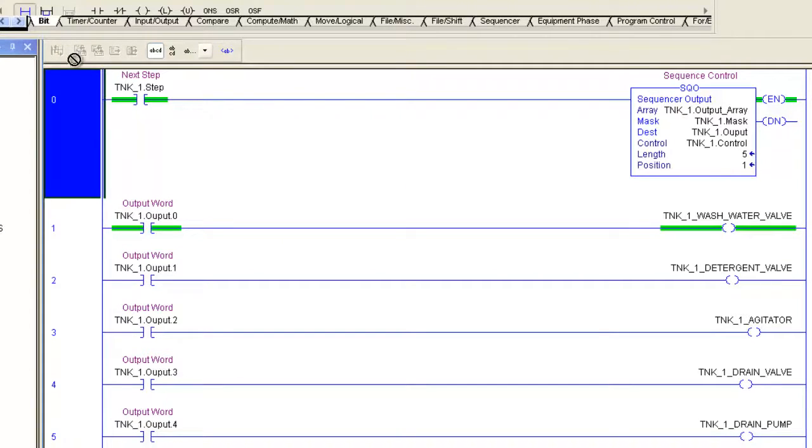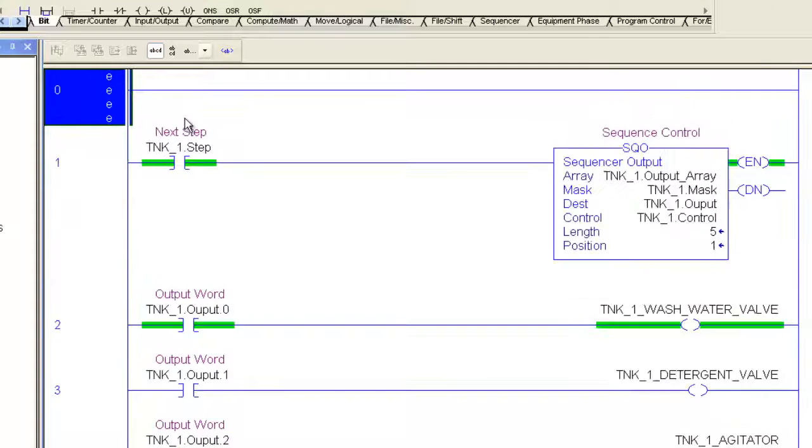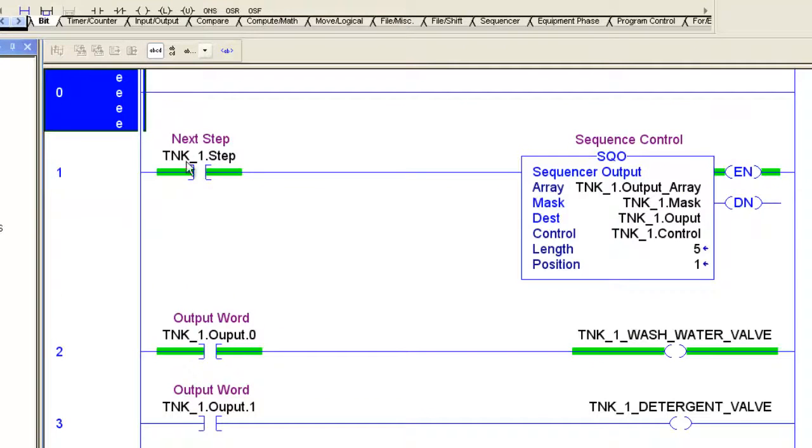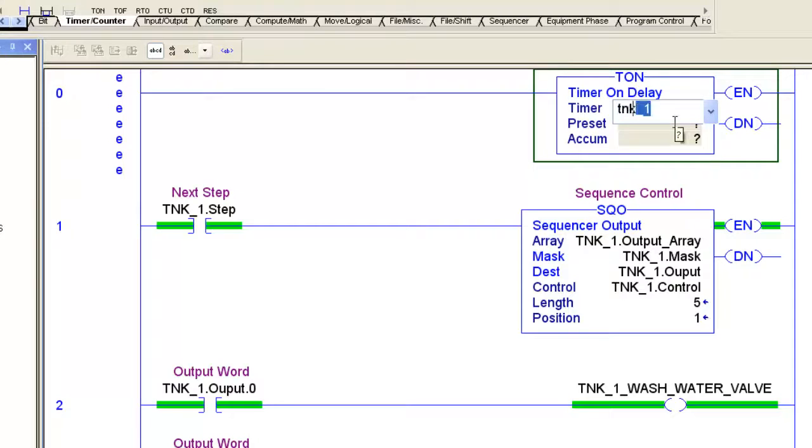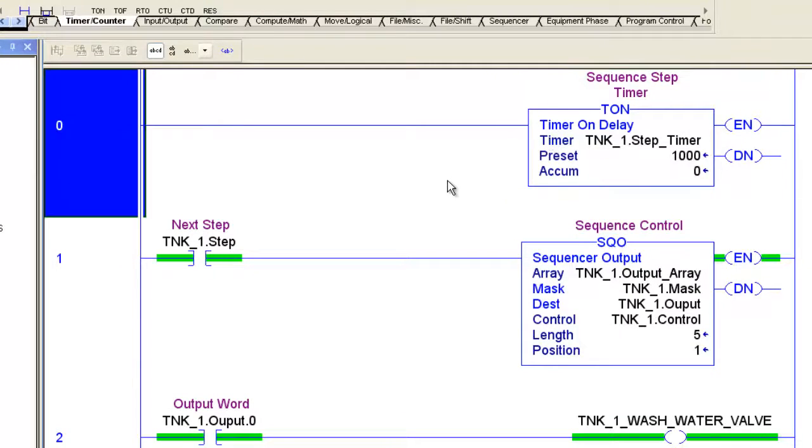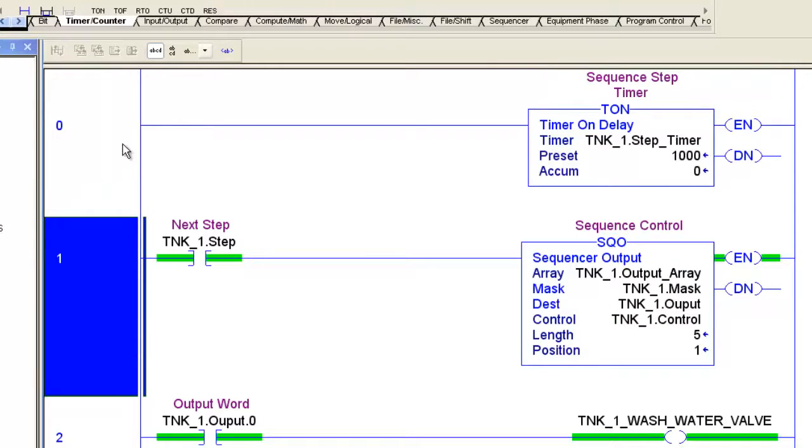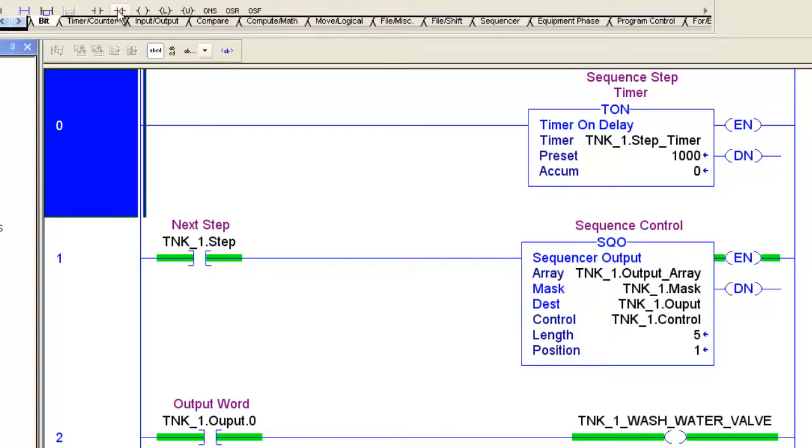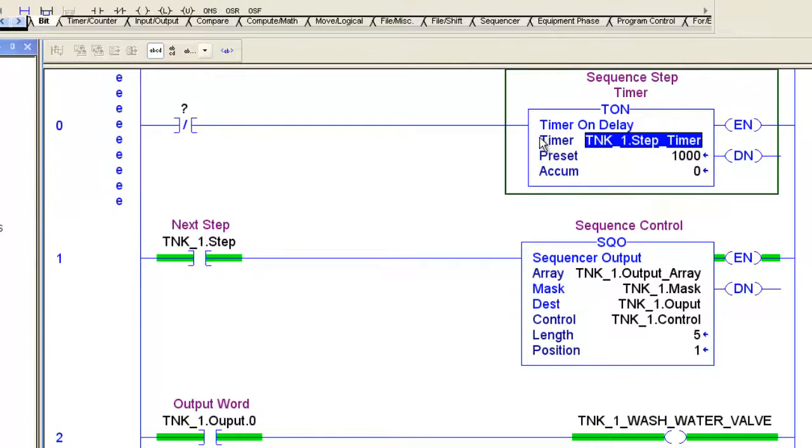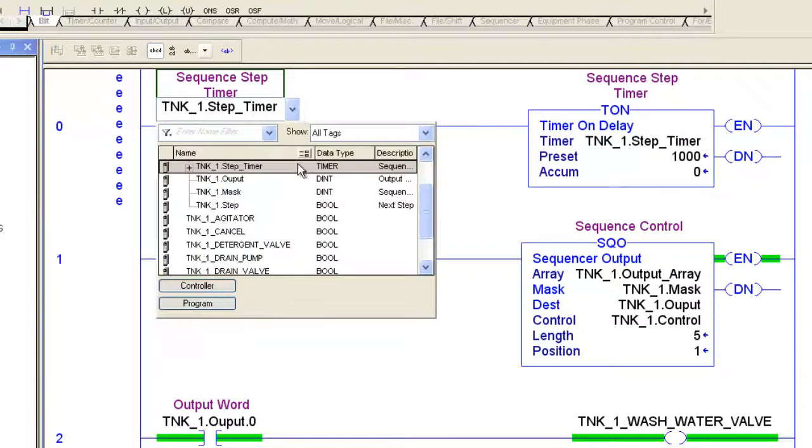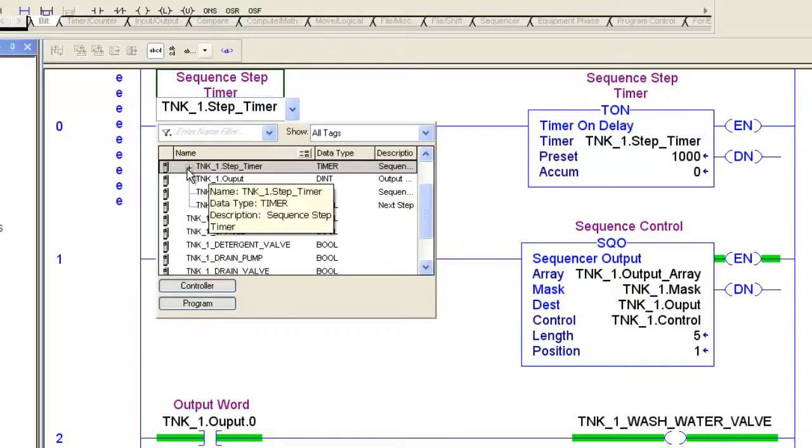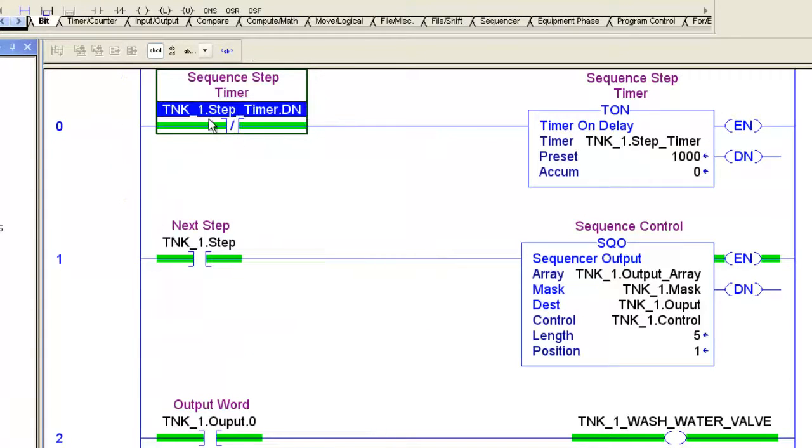So in order to make this happen, I want the tank1 step to be initiated at a certain time interval. I'm going to add a rung here. I'm going to put my timer instruction and search for my tank1.steptimer and we'll just put a one second in there for now. And then we'll use this timer done bit to reset itself. So every time a second elapses, the timer done bit will turn on which will reset the timer. Pretty simple.